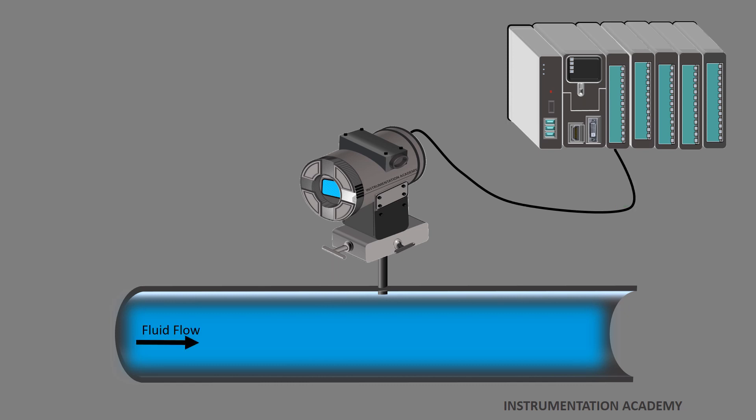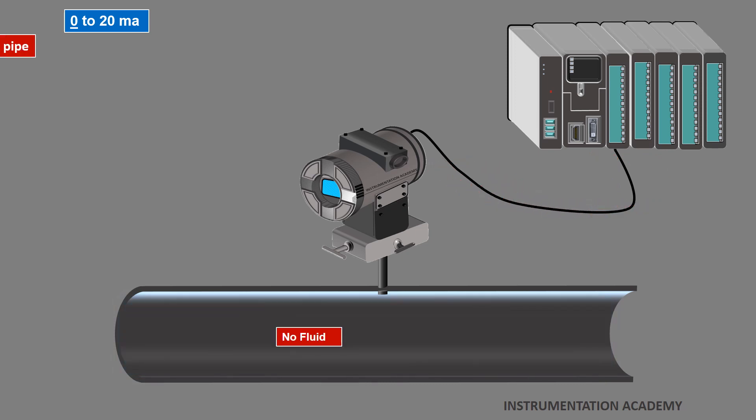Now consider the other case that fluid passing through the pipeline exerts pressure in the range of 0 to 10 bar and the transmitter is calibrated to generate current signal in the range of 0 to 20 mA. When there is no fluid flowing through the pipeline, the transmitter generates 0 mA current at the output terminals.